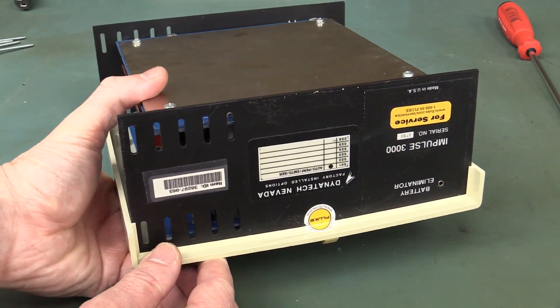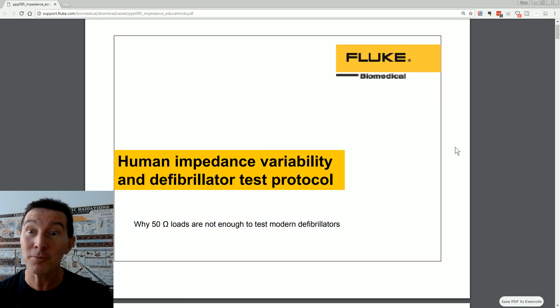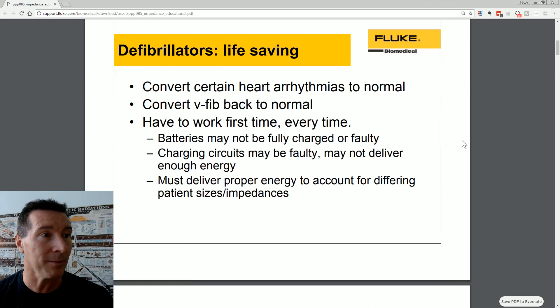I just found the user manual for this thing on the Fluke website. I don't know, maybe Fluke did offer it or something like that - certainly not Fluke branded though, in the manual or on the device itself. But check this out: I found this on the Fluke Biomedical Division page - it's a paper on Human Impedance Variability and Defibrillator Test Protocol, and why 50 ohm loads are not enough to test modern defibrillators. Remember, the model we're looking at is 27 years old. That's why it had the Fluke calibration sticker - it would have been calibrated by the Fluke Biomedical Division.